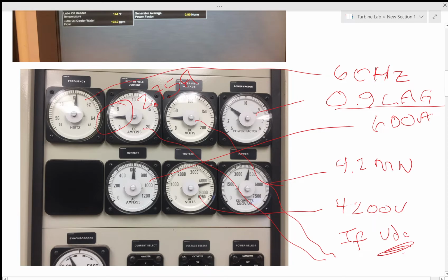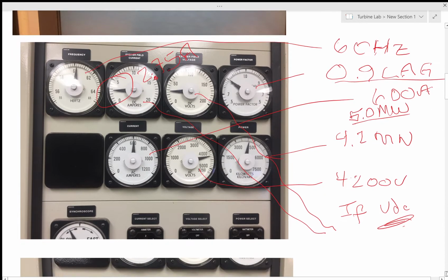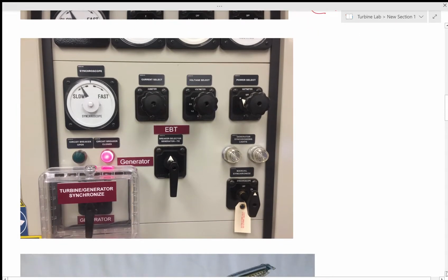And this is automatic. As the turbine ramps up, we put more and more current into it, and we get more and more power out until we reach the maximum power, which this turbine is rated for 5 megawatts. And the only time I've ever seen it get to 5 megawatts was when it was minus 11 degrees outside. So pretty impressive machine. It's very well controlled. The guys at the central plant do a pretty good job of it. And those are the controls. And we get feedback from that. That feeds into our Niagara system and tells us what's going on. At the end of this little slideshow, I'm going to show you what happens when you don't sync in. Anyway, these are all the synchronous controls.